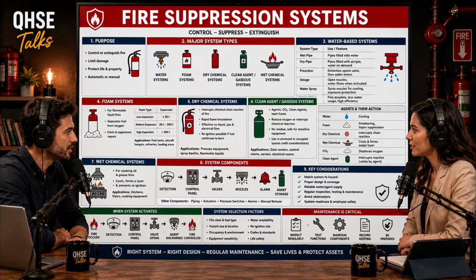I want to make sure I understand this because it sounds like a 2-factor authentication process for a sprinkler. You need 2 separate events to occur to get water on the fire. That is a brilliant analogy. It is exactly like 2-factor authentication. Let's walk through it. Step 1. A smoke detector on the ceiling senses a fire. It sends a signal to electronically open the main water valve in the riser room. So the valve opens and water rushes into the overhead pipes.